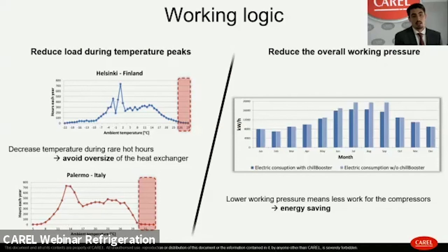On the other hand, another logic that can be pursued is to achieve a better efficiency. You see in the histogram that the consumption is different using the chillBooster or not. And in this case, it's especially true with CO2, because with chillBooster we can operate at a lower ambient temperature, working a higher quantity of hours in subcritical condition.